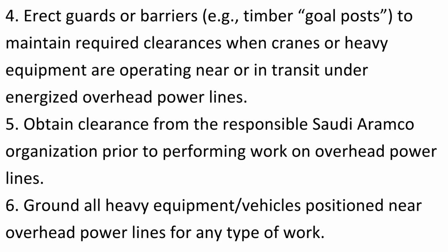4. Erect guards or barriers, for example timber goalposts, to maintain required clearances when cranes or heavy equipment are operating near or in transit under energized overhead power lines. 5. Obtain clearance from the responsible Saudi Aramco organization prior to performing work on overhead power lines. 6. Ground all heavy equipment vehicles positioned near overhead power lines for any type of work.